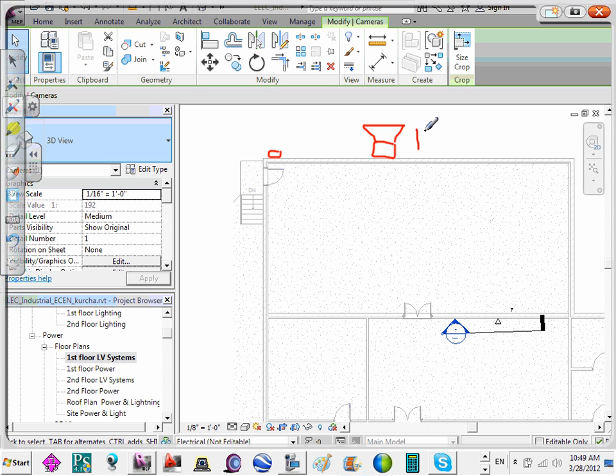But typically the horn strobe is going to be tied into the sprinkler system. It's going to be a 120 volt system, a 120 volt horn strobe. We usually don't provide that. It's either the sprinkler contractor, because that's going to be tied right into the flow switches. So if that's going off, it starts beeping, letting the fire department know here's where you're going.